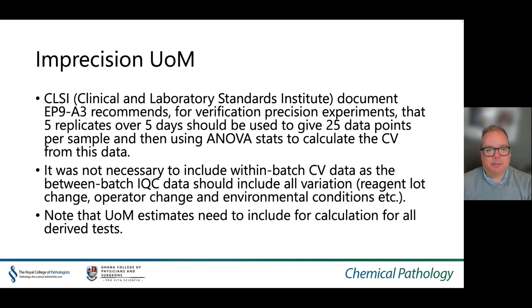There are recognised standards available for this. CLSI standard EP9-A3 recommends for verification precision experiments that five replicates over five days should be used to give 25 data points per sample, then analysed using ANOVA to calculate the CV. It is not necessary to include within-batch CV data as the between-batch IQC data should include all variation — reagent lot change, operator change, and environmental conditions, for example.